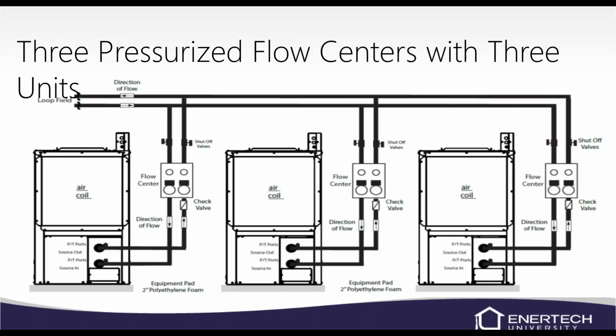If you have three units and you want to tie them all into the same loop field, then you would have to have individual flow centers for each unit. Make sure that you are installing check valves at the flow centers and also shut-off valves, so if you need to isolate and change out a pump or something like that, you can. But any more than two units, you have to get another flow center, basically.